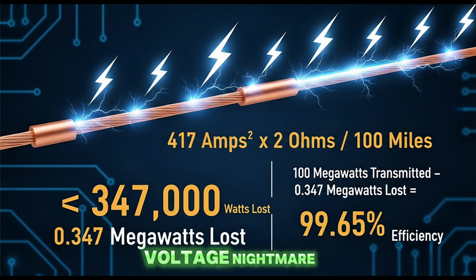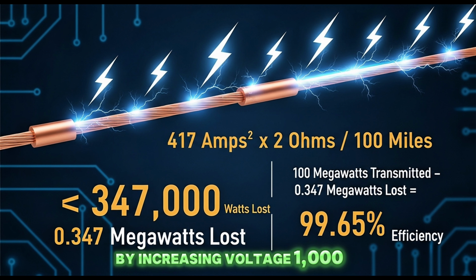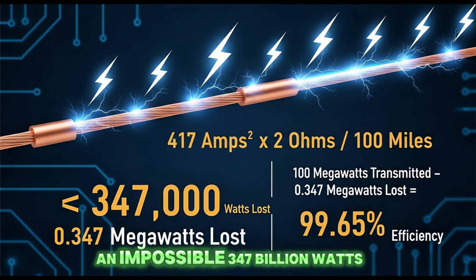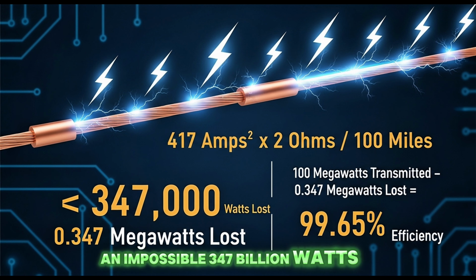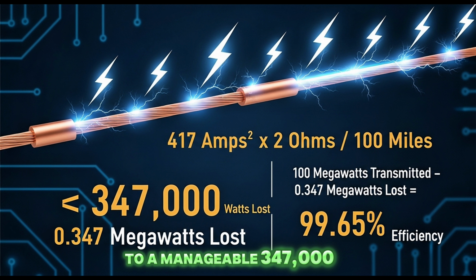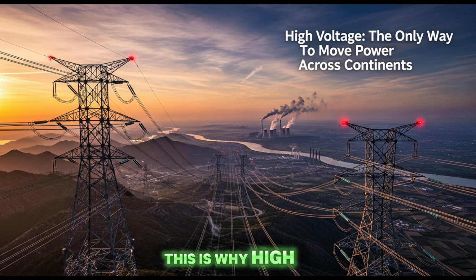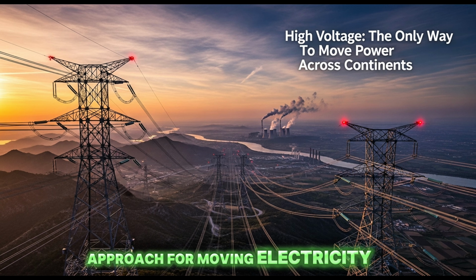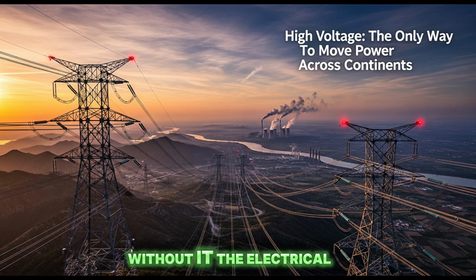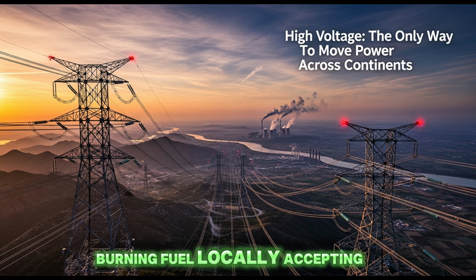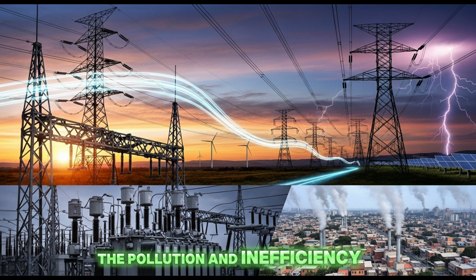Compare this to our low-voltage nightmare. By increasing voltage 1,000-fold, we reduced losses from an impossible 347 billion watts to a manageable 347,000 watts. That's a million-fold improvement in efficiency. This is why high-voltage transmission isn't just better, it's the only viable approach for moving electricity across continents. Without it, the electrical grid as we know it couldn't exist. We'd be limited to power plants in every neighborhood, burning fuel locally, accepting the pollution and inefficiency because distant transmission would waste more energy than it delivered.